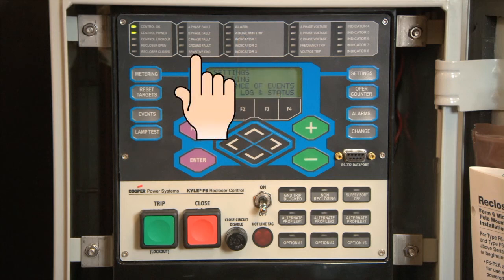Sensitive ground earth fault operation. The control has a sensitive ground earth fault trip feature that provides tripping of the recloser after a programmable definite time for ground currents below normal ground minimum trip levels. The feature has programmable operations to lock out and reclose intervals independent of the ground settings. This feature is independently selectable for each protection profile.